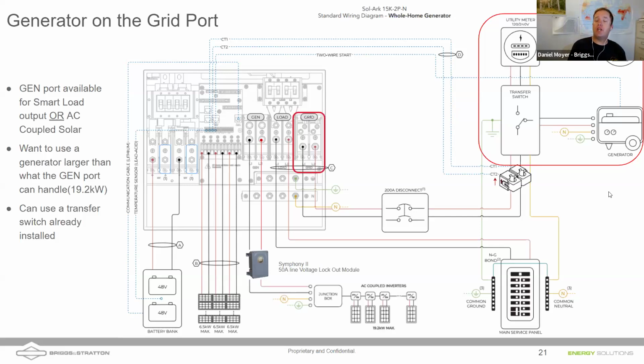So we can either program the generator to not run during solar hours, or we can leverage one of our Symphony II load shedding modules to be a lockout module, so that if the generator comes on, that line contactor is going to open up, preventing that AC coupled solar, whether it's a SolarEdge or an Enphase, from ever operating while the generator is functioning. And these lockout modules are relatively cheap as well, as long as you have a Symphony 2 or a Symphony Choice transfer switch. Yep, you can purchase one of these. I think they're between $100 and $200.